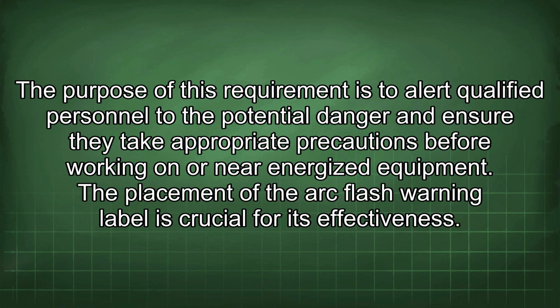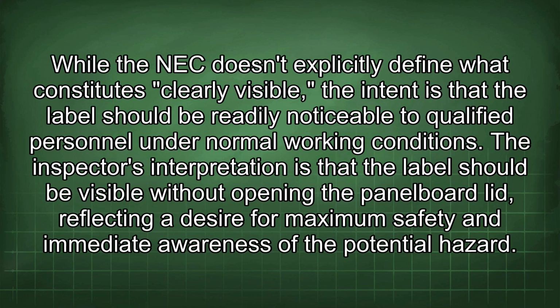The placement of the arc flash warning label is crucial for its effectiveness. While the NEC doesn't explicitly define what constitutes clearly visible, the intent is that the label should be readily noticeable to qualified personnel under normal working conditions. The inspector's interpretation is that the label should be visible without opening the panel board lid, reflecting a desire for maximum safety and immediate awareness of the potential hazard.